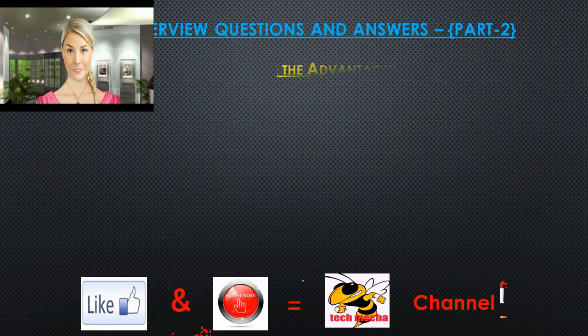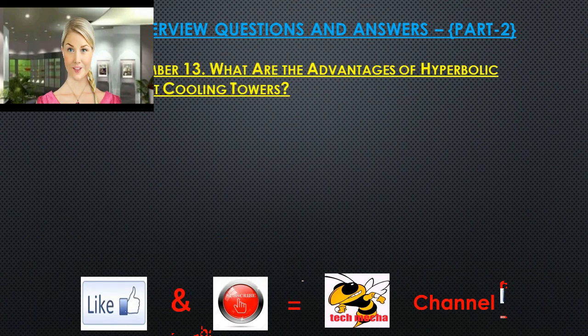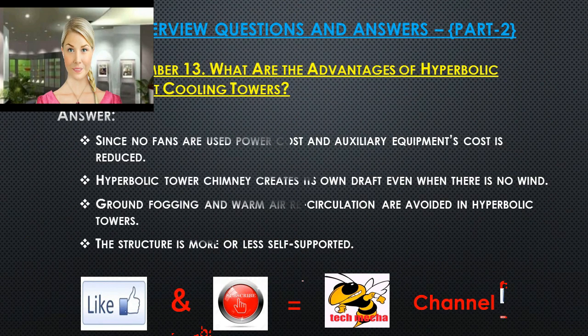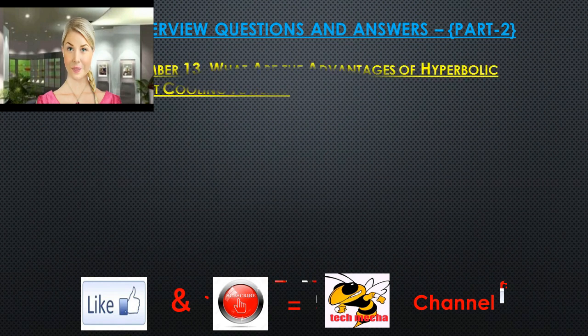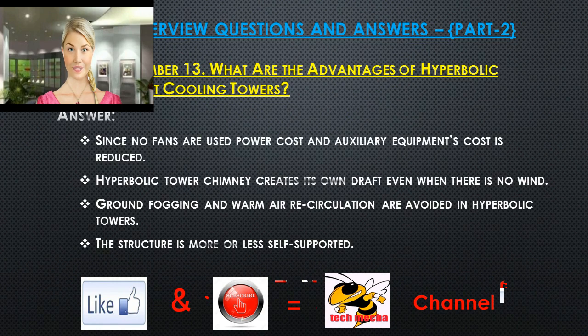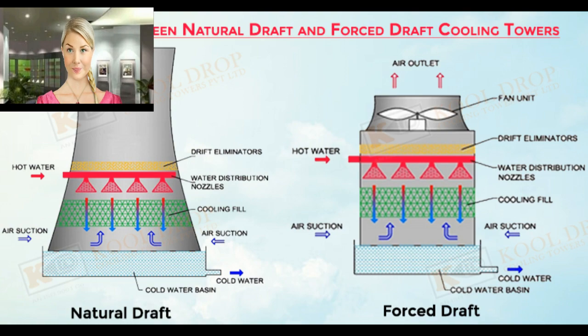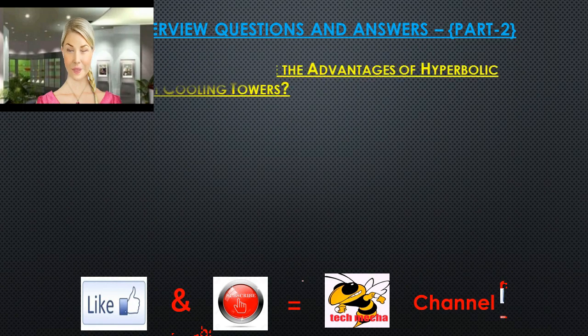Question 13: What are the advantages of hyperbolic natural draft cooling towers? Since no fans are used, power cost and auxiliary equipment costs are reduced. The hyperbolic tower chimney creates its own draft even when there is no wind. Ground fogging and warm air recirculation are avoided, and the structure is more or less self-supported.